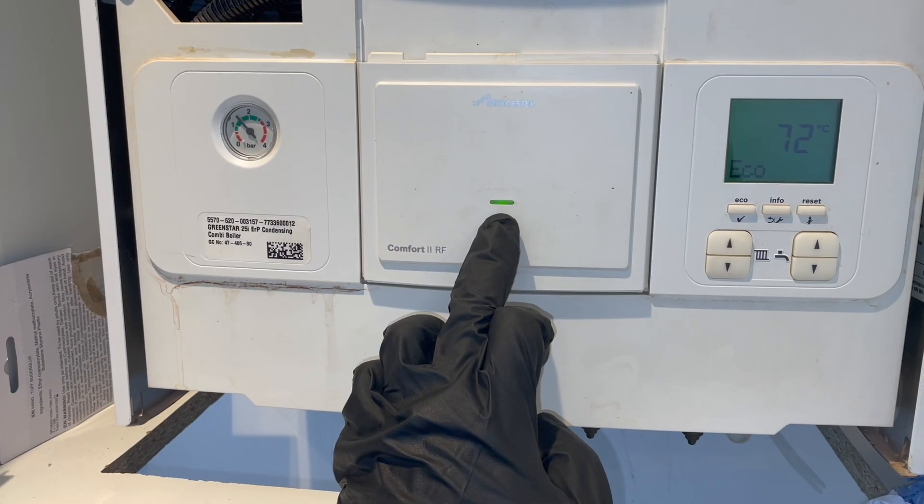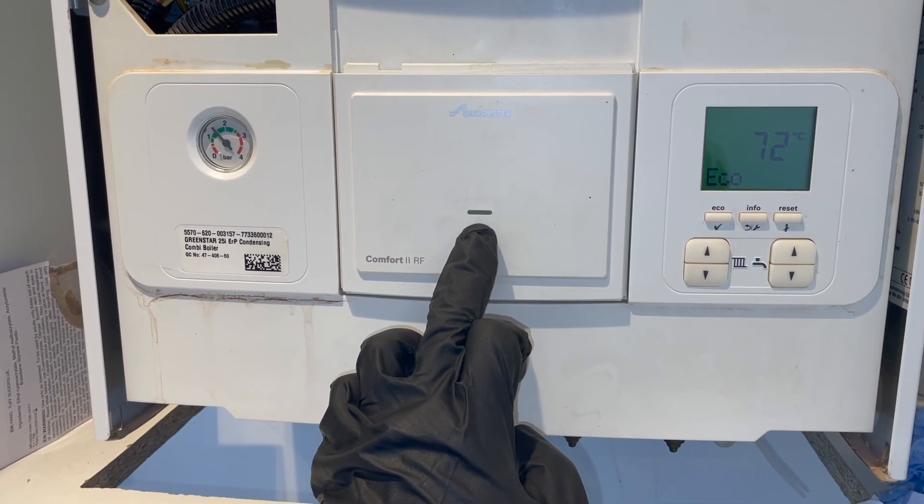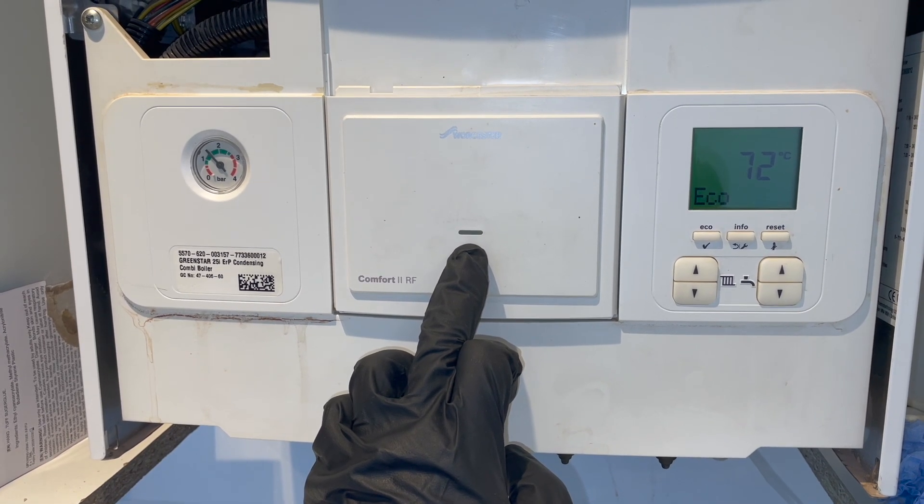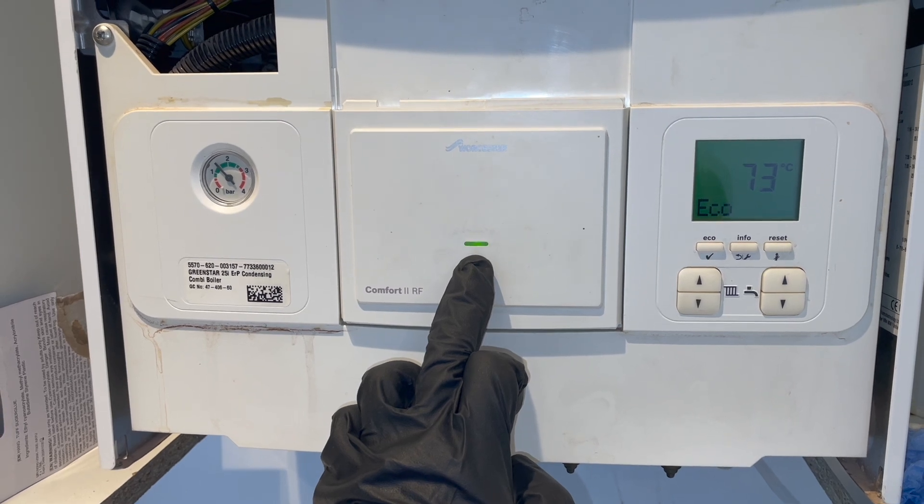What we're going to do is unpair the connection between the receiver and the thermostat, and then re-pair them. We're going to do that by pushing and holding the override button on the receiver until we see five fast flashes.